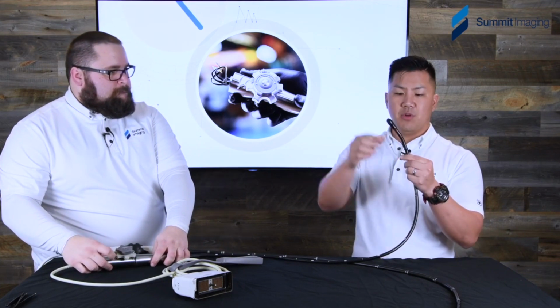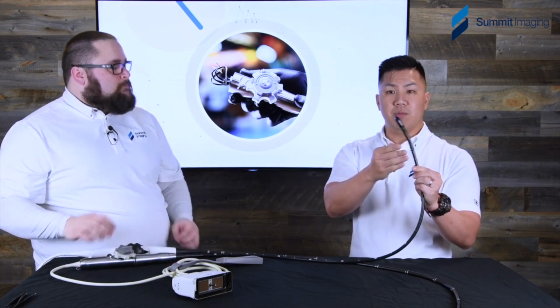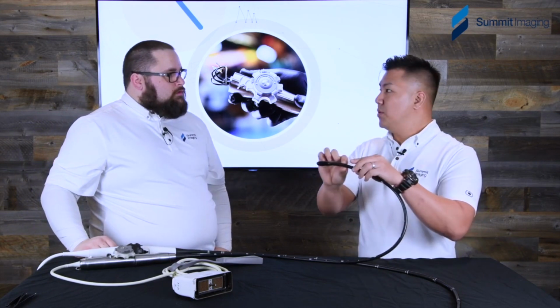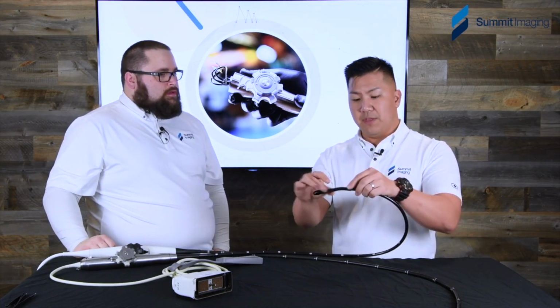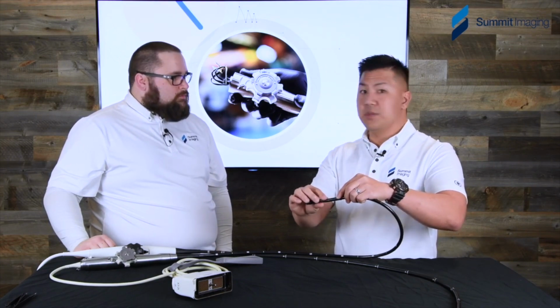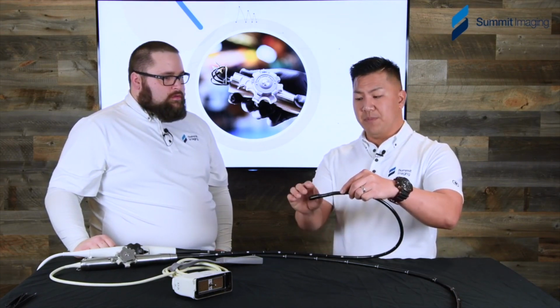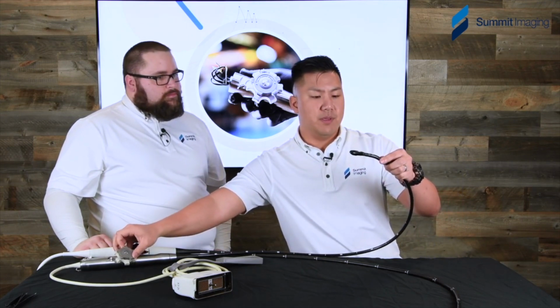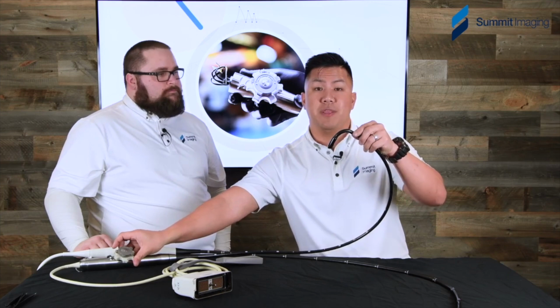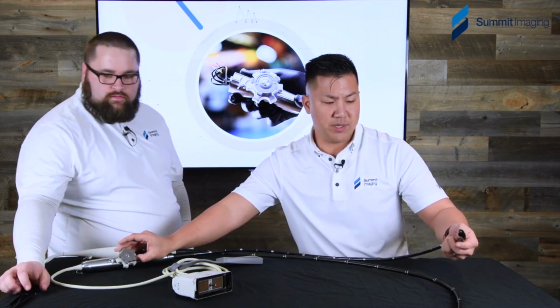So even if the process goes through perfectly, we really recommend that final visual and really just manipulating the bending section of the TEE probe here, because by virtue of it being rubber, if it's going into the leakage tester straight, if there is a pinhole on this side, it may actually close itself when it's straight, but the moment that you articulate it forward, it may stretch that hole out, and then fluid starts getting in, cross-contamination, leakage failure, all that. But you have to kind of induce the issue prior to actually using it on the patient again. So we really recommend that visual test again to do that, or even manipulating it during the leakage test is a really great idea to expose those issues.